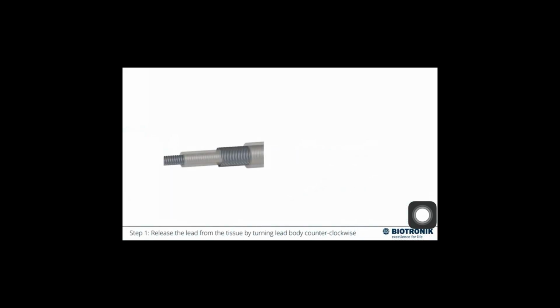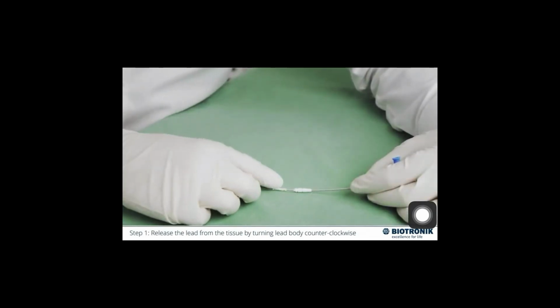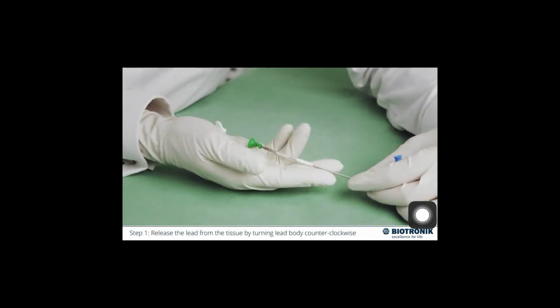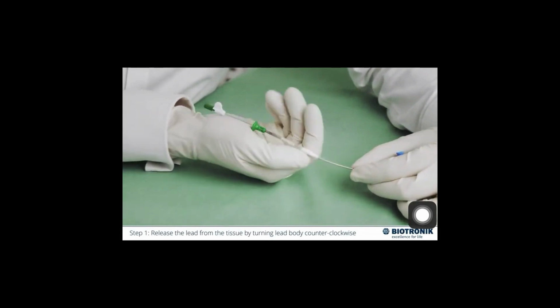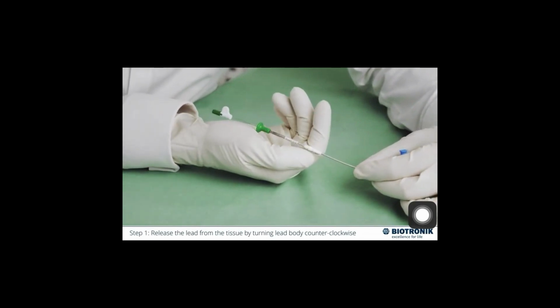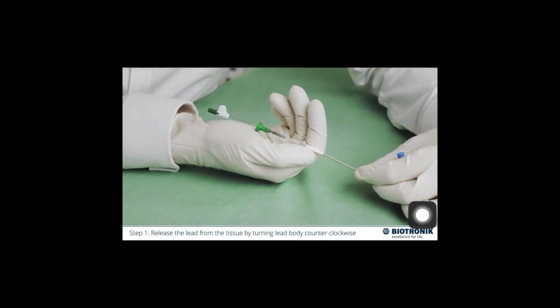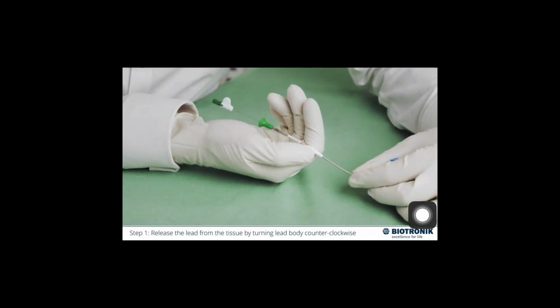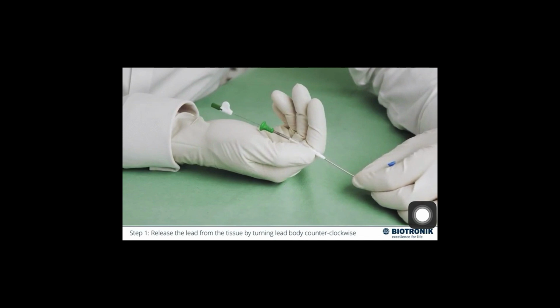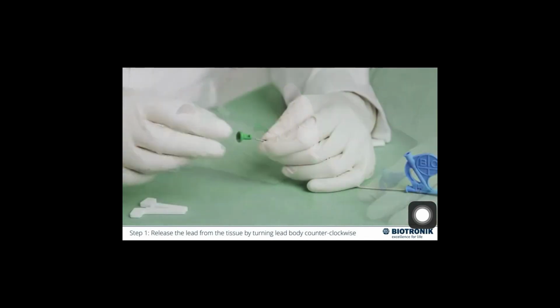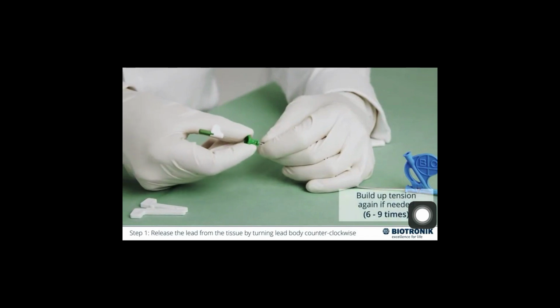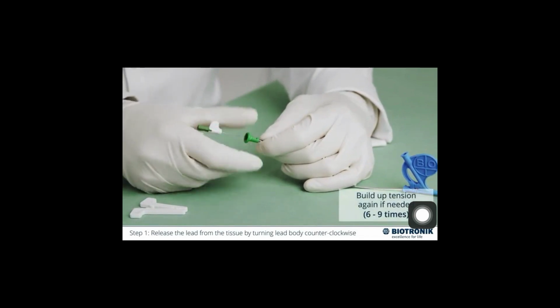To remove the lead from the tissue, it is important that there is tension on the inner coil and that the helix is completely exposed. If the green stylet guide is still firmly attached to the connector pin, the lead body can be counter-rotated slowly, avoiding high tensile forces. If the green stylet guide was removed, reattach to the connector pin and rotate the stylet guide 6 to 9 times clockwise before lead removal.